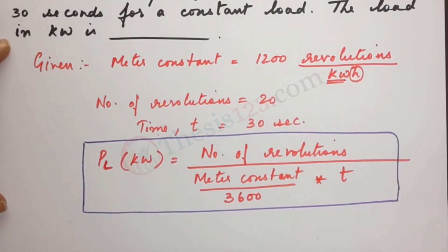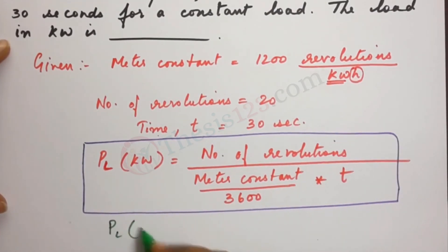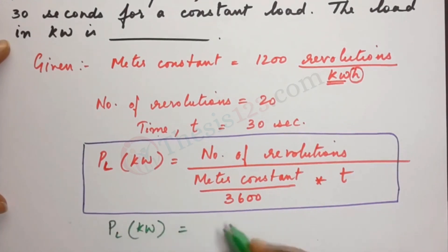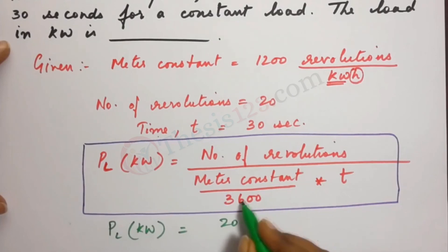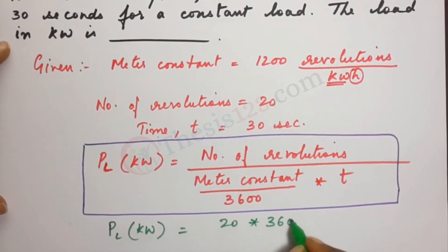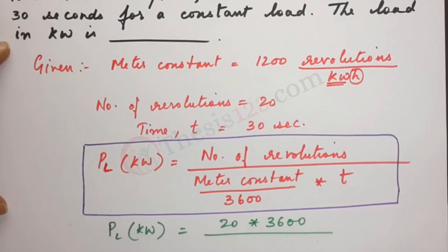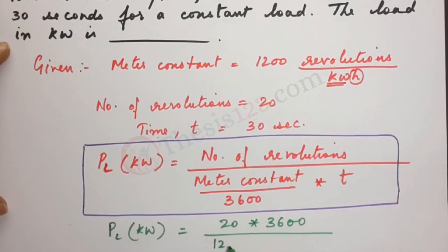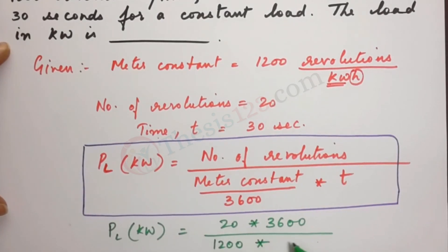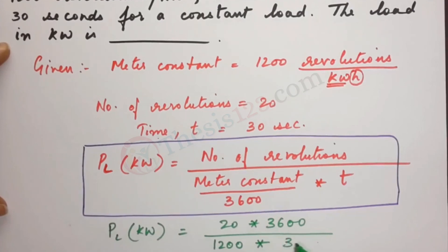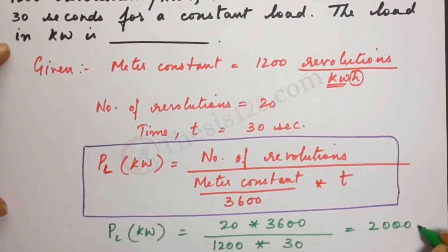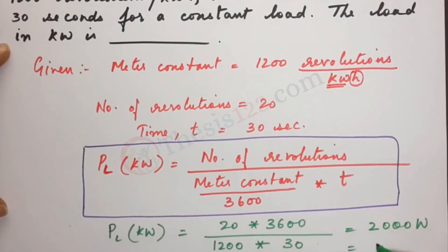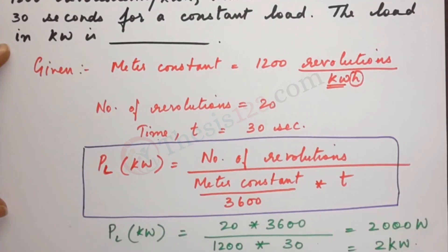Okay, so let's substitute the values now. We will have PL kilowatts is equal to 20 number of revolutions, and since we have 3600 that goes up to the numerator divided by the meter constant of 1200 into time we have 30 seconds. This gives us 2000 watts which is in terms of 2 kilowatts.